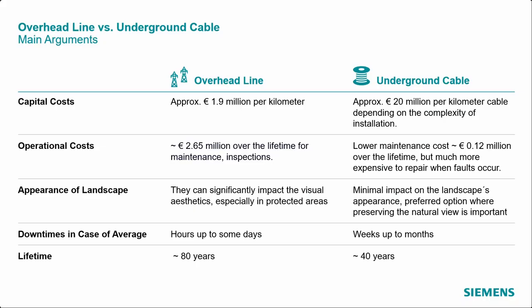As faults in overhead lines are easier to localize, it reduces the downtimes. However, since they are in open-air conditions, it makes them more susceptible to being damaged from storms, lightning, and other weather conditions. On the other side, faults in underground cables can be harder to localize and repair, leading to longer downtimes.